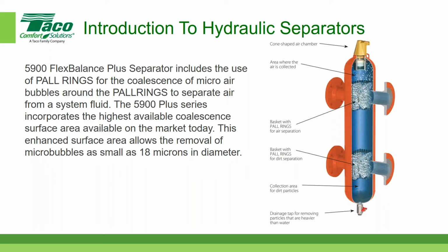So if you have air bubbles on the bottom, will they go up into the high water stream? The dirt's going to fall down. Yes, the air will actually pass through the Pall rings in the upper basket, and they won't get caught there. I think that's what they're asking. And vice versa with the dirt. The dirt's got to go through. No, the dirt, because what actually, yeah, I think I understand.